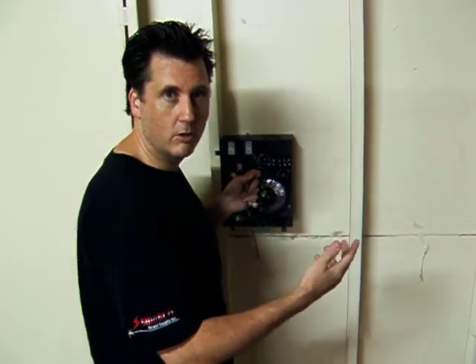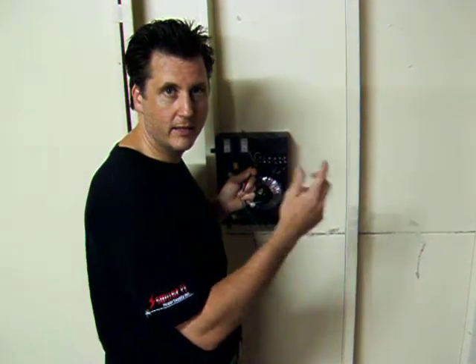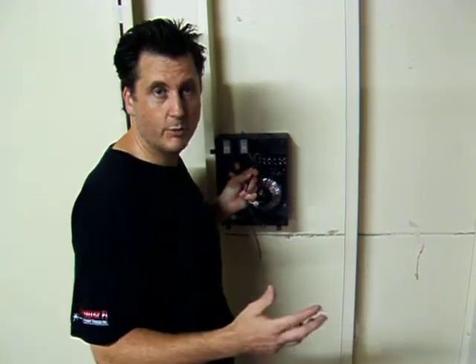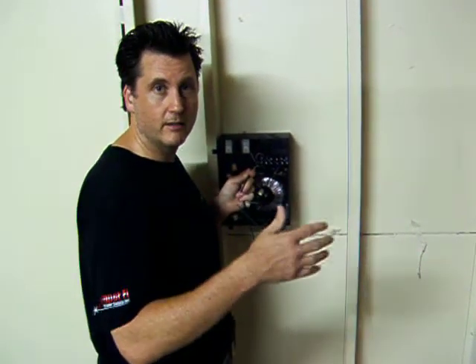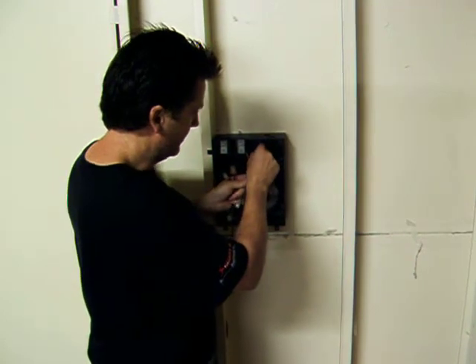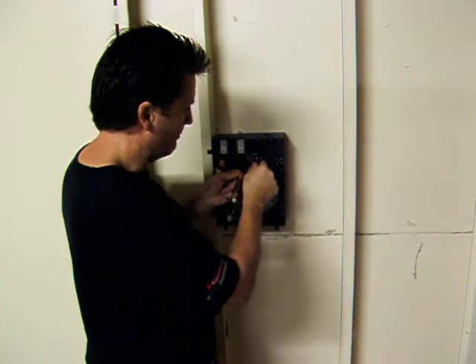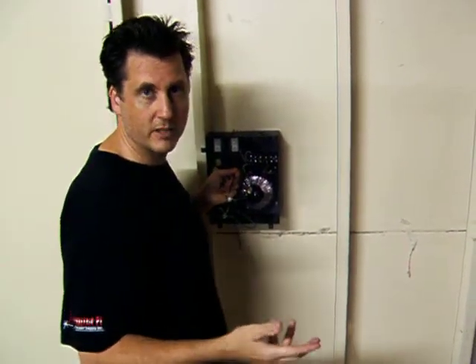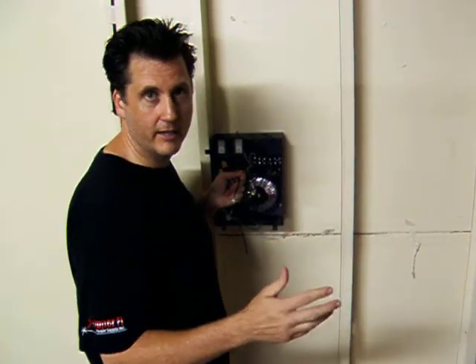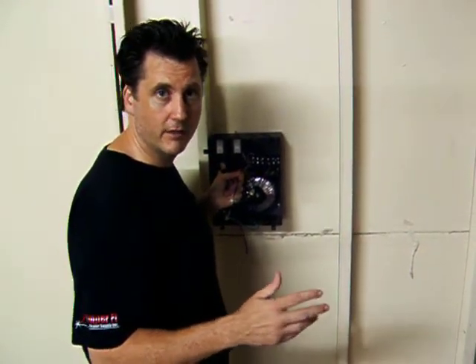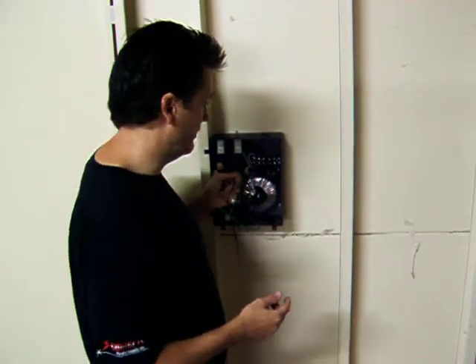So if I put my dimmer at full bright, I go to the load and I measure 11.2 volts. I know that to get to 12, that's 0.8 volts. So I would basically take this and I would go up 1 tap. And that will raise it approximately a half a volt. So you should be around 11.5, or 11.7, 11.8 with the dimmer at full bright.